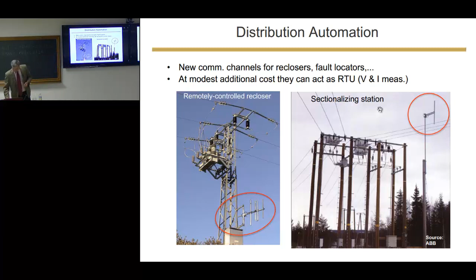Also control power electronic devices. We, for instance, have been promoting, in this group, the use of a back-to-back voltage source converter linking asynchronously one feeder with the neighbor feeder. This is one feeder, this is another feeder, and we can link the two feeders with a DC link, an asynchronous link, with two back-to-back converters that have 3 degrees of freedom. You can control freely, within the ratings of the device, the active power flowing from one feeder to the neighbor. We can control at the same time the two reactive powers on both sides so that we can regulate the voltages on both sides. So these are 3 degrees of freedom.